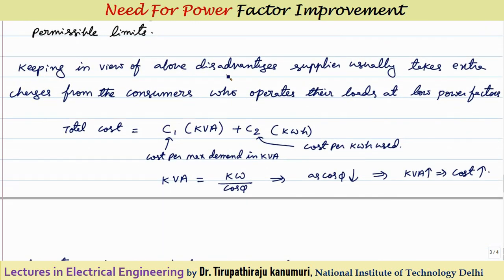Keeping in view these disadvantages, the supplier wants the power factor to be unity — so that fixed costs, variable costs, and losses are all reduced and the line is used effectively. That is why they discourage consumers operating at low power factor by charging extra. Generally, if the power factor is maintained below 0.8, a fine is imposed, and a two-part tariff is applied.